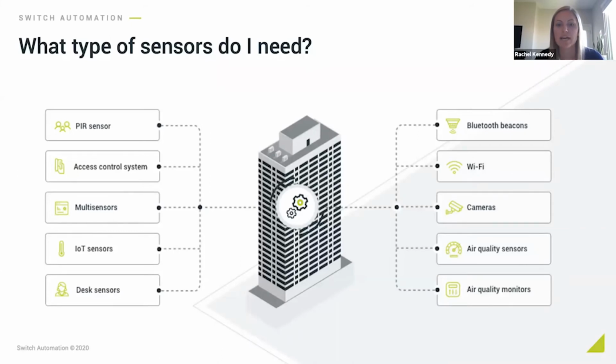With the PIR sensors and the access control system, as I said, some of these are already existing, but they often tend to be at lower granularity. If we're thinking about those different resolutions, we're looking at some of the more one per space or one per building. So you don't have that high density that you would need for a heat map, let's say.